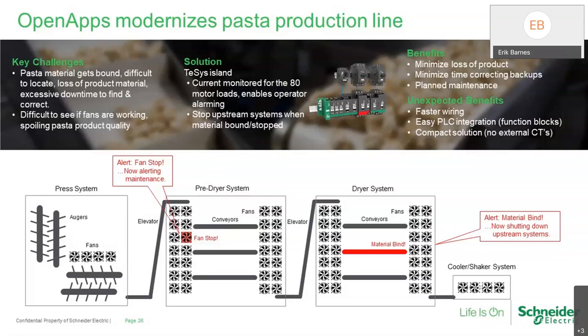One of the issues is that if the fan stops and doesn't operate, the starter is pulled in, the PLC thinks it's running, but it's not running. They don't know that because it's not visible. So the way they find out is that their product quality starts to deviate. They wonder why the product is not meeting quality standards, then they go to investigations. Oh man, there are 3 fans here that aren't working. With Island, we can totally detect those things.